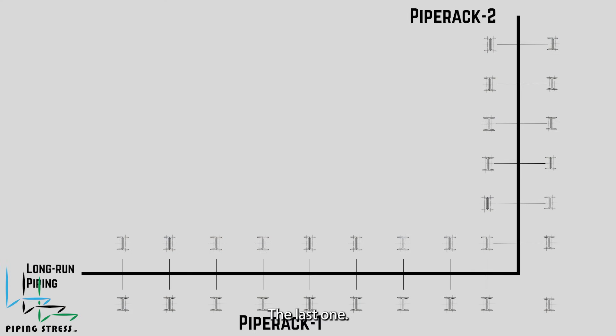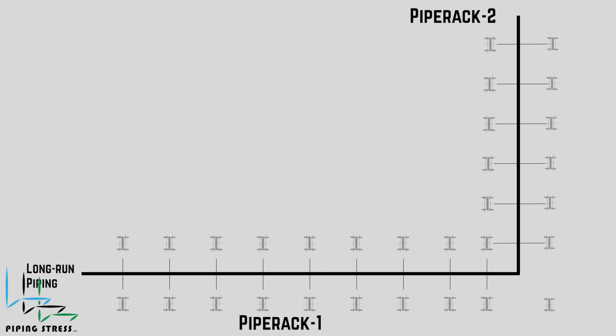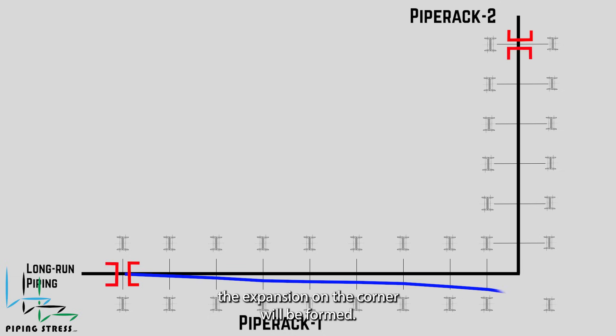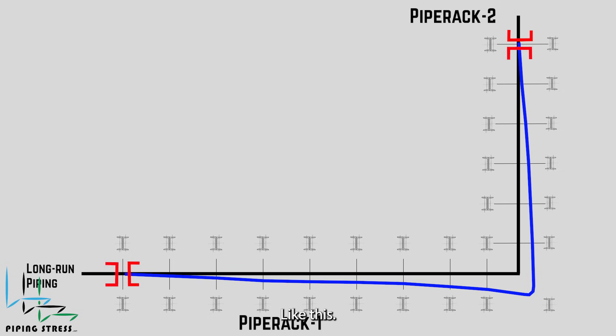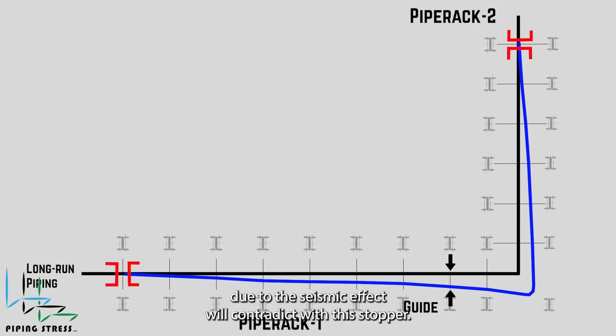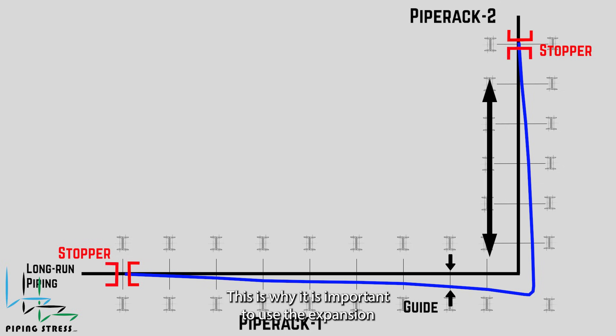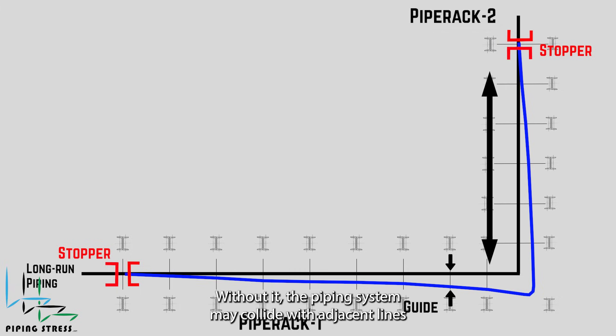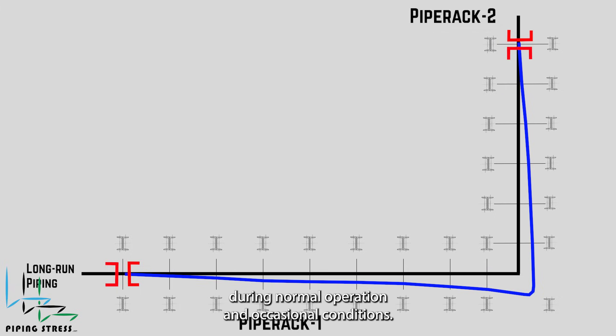Consider that two pipe racks are perpendicular to each other. If we put the pipe stopper at the natural zero point, the expansion on the corner will form in a specific way. Any guide requirement here, due to the seismic effect, will contradict this stopper. This is why it is important to use the expansion loop to manage expansion with the help of restraints. Without it, the piping system may collide with adjacent lines during normal operation and occasional conditions.